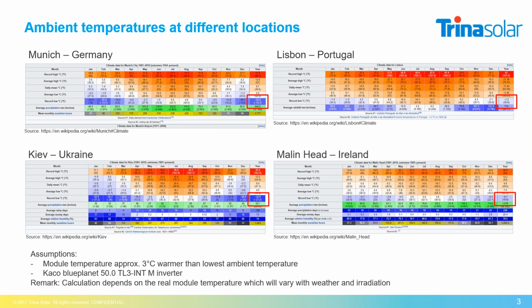For this study, I assume that the module temperature is approximately 3 degrees warmer than the lowest ambient temperature, because during the day the temperature is slightly higher than at night. I also assume the system is running on a very cloudy, dark day where it is really cold during the day, and then the clouds break and the sun comes out directly, giving a certain level of irradiation, which means you directly jump to a very high voltage level. Further, I used an inverter, in this case a Kaco inverter, which is able to have a system voltage of up to 1100 volts. Since this is completely individual, it depends on the information you have on the climate, the ambient temperatures, and the irradiation. Therefore, it is really location dependent.